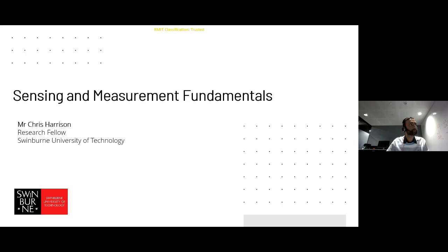So if we imagine a system, right? We have a black box that's measuring our thermocouple. Our thermocouple exists somewhere in our setup, and there are these two wires of different metals that are bonded together at the very end of that thermocouple. And what we want to measure is the very small voltage generated by that junction. Those wires come back into your magic black box that does your thermocouple measurement. And what exists at that boundary? Probably a connector, and that connector probably has dissimilar metals in it. The metals used to make thermocouples are usually esoteric alloys, alumel and weird things. But they're probably going to go onto a circuit board, and circuit boards have copper traces.